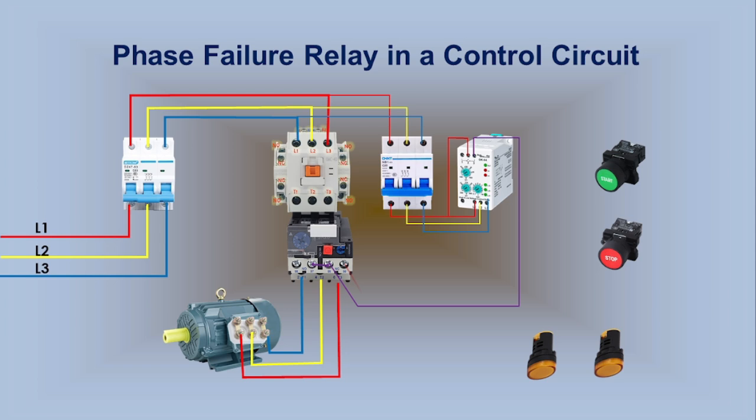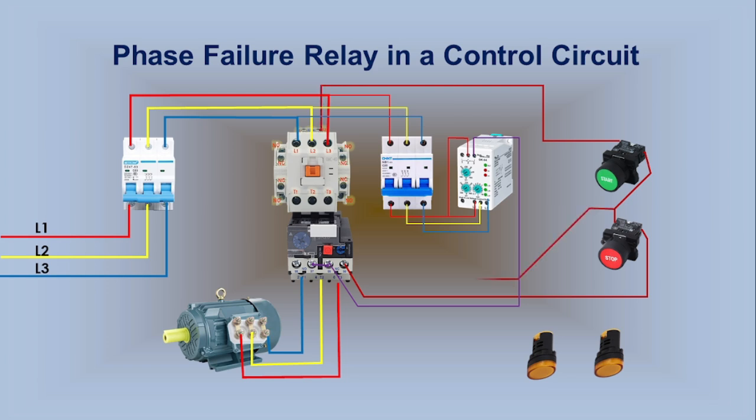Terminal 95 of the Overload Relay is next to Terminal 96. Terminal 97 is normally open to Terminal 98. A wire runs from Terminal 96 to the Stop Push Button. Terminal 96 is normally closed and is part of the Overload Relay. The second terminal of the Stop Push Button connects to the Start Push Button. A wire runs from the second terminal of the Start Push Button to Coil Terminal A2 of the Magnetic Contactor. The normally open auxiliary contact of the Magnetic Contactor also connects here, and its second terminal connects to Coil Terminal A2.